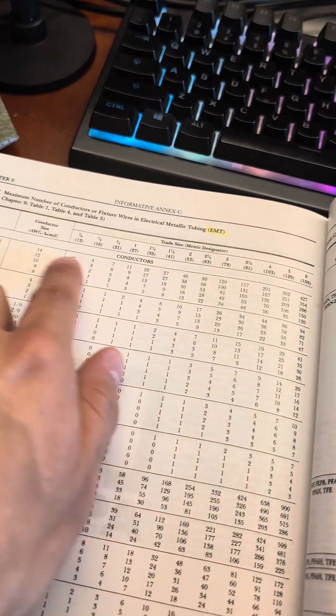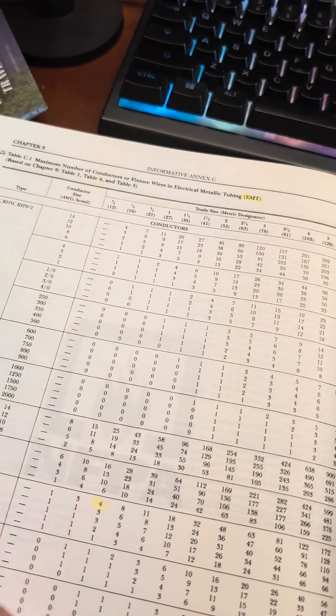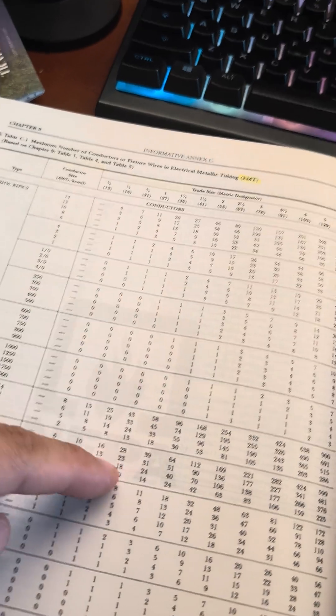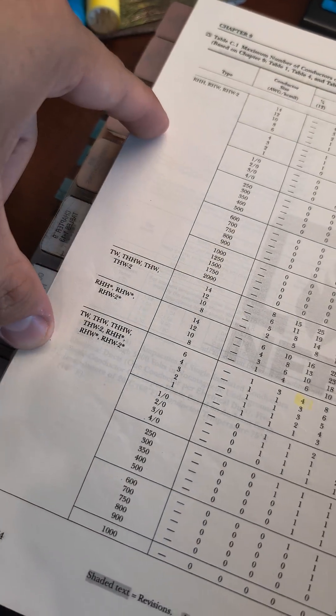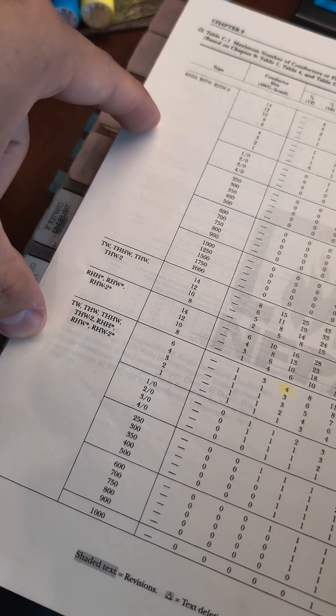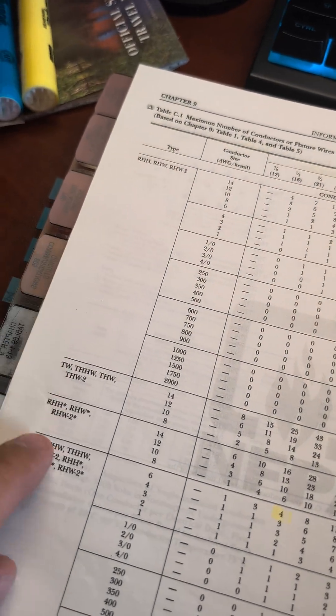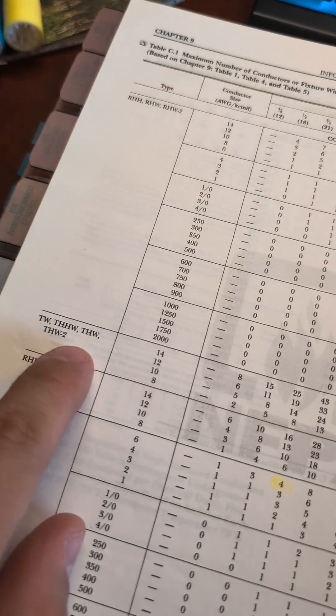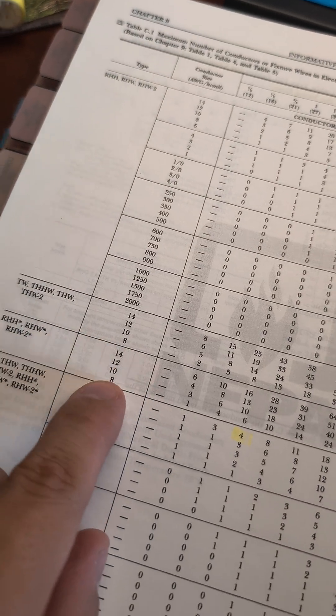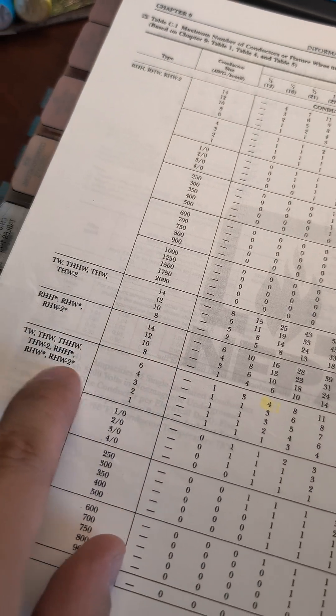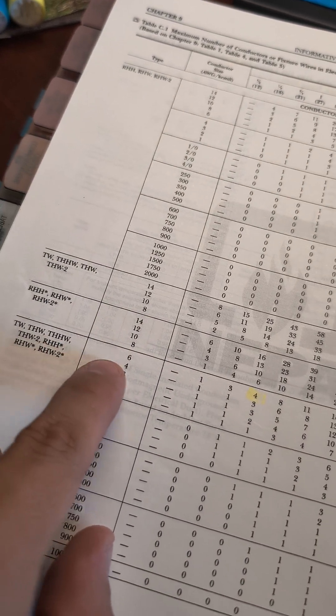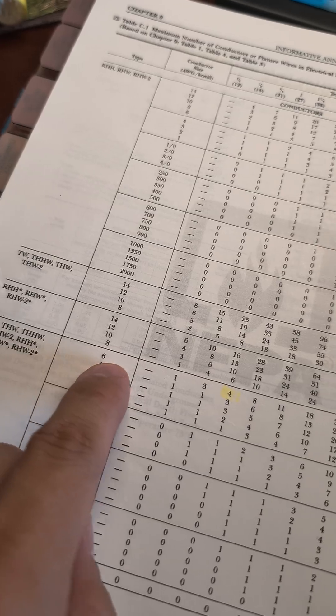And so how this table works is you have your trade sizes across the top. These are the number of conductors you can fit in there, and then these are the conductor insulation types. We're looking for THHW, which is here, but we're also looking for number six. So we're going to have to go down to the next section, which is here, number six.